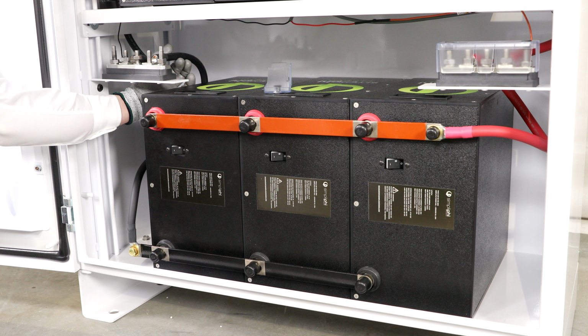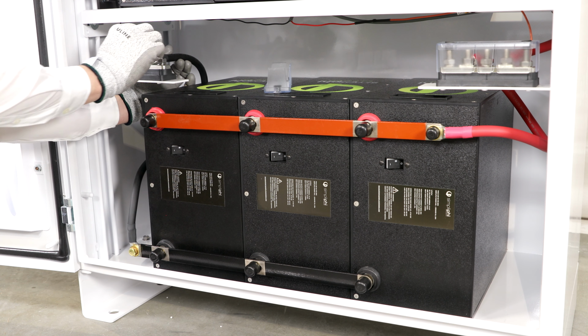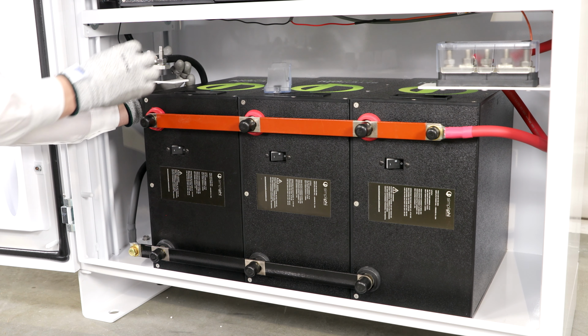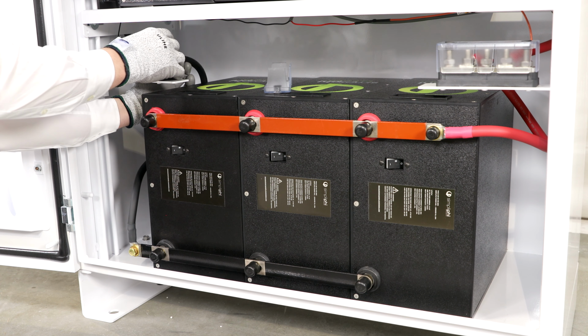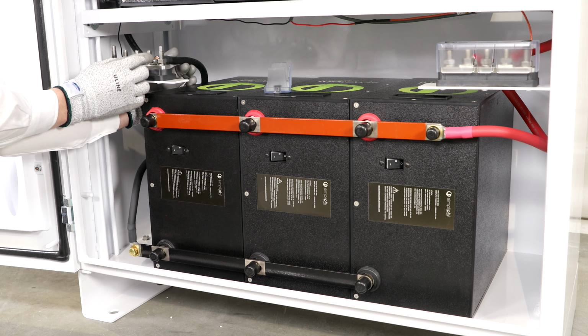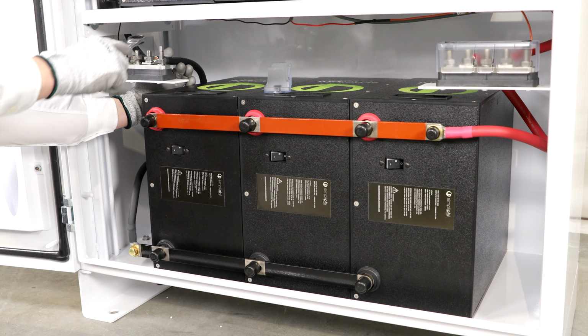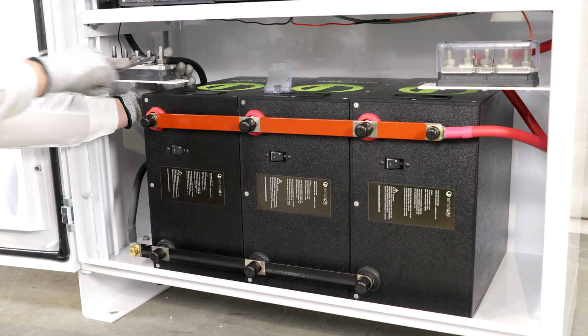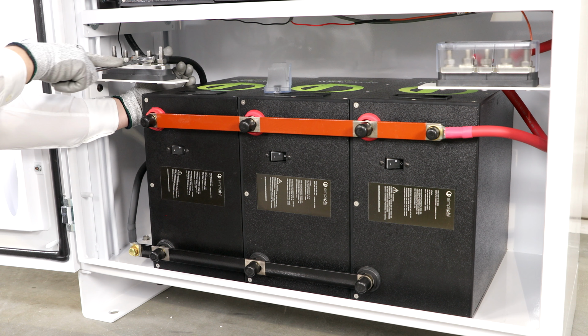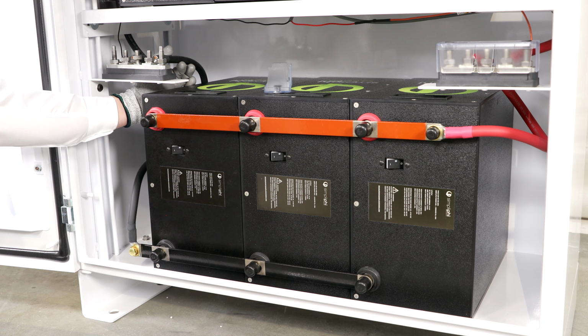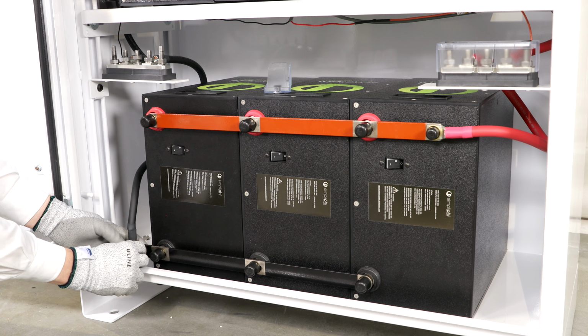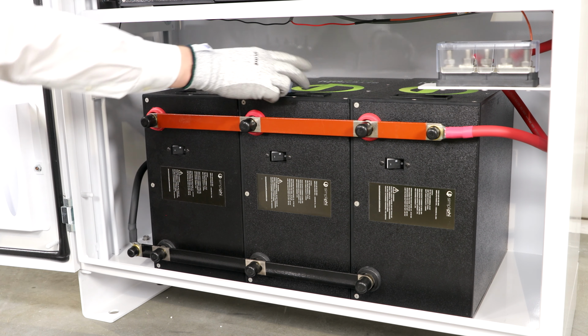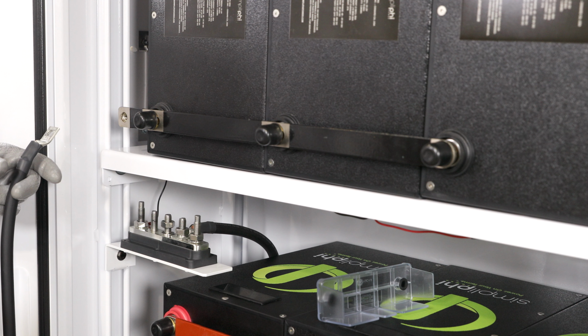When routing the cabling, be careful not to damage the small wire that is already attached to the 5-point terminal block. This wire routes from the terminal block to the venting fan. Attach the cable's lug to the 5-point terminal block, followed by the lock washer and nut that were removed earlier. Firmly tighten the nut to secure the cabling lug to the 5-point terminal block. After securing the lug to the bus bar, place the black bolt cover over the brass hex bolt. You are now ready to secure the top negative bus bar to the 5-point terminal block.